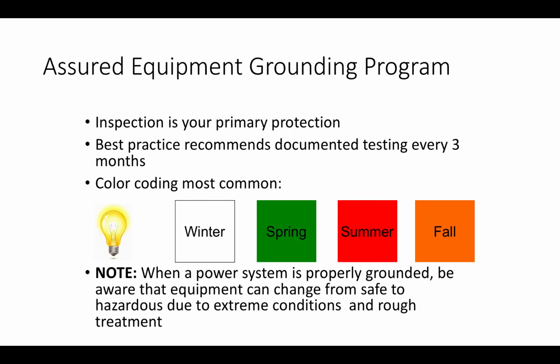We need to have an assured equipment grounding program. Inspection is your primary protection. Best practice recommends documenting testing every 3 months. Okay, color coding in this documentation is very common. We have winter, spring, summer, and fall. When a power system is properly grounded, be aware the equipment can change from safe to hazardous due to extreme conditions and rough treatment. Don't assume, always check.